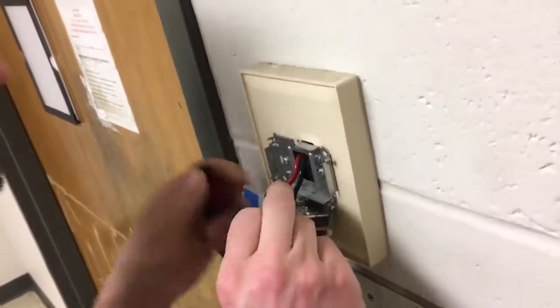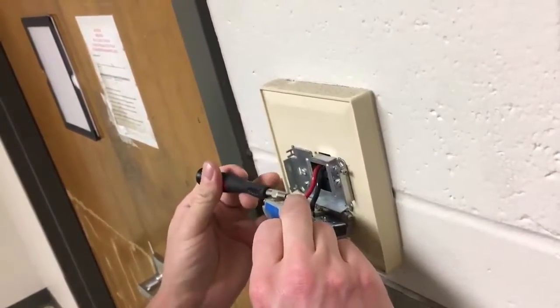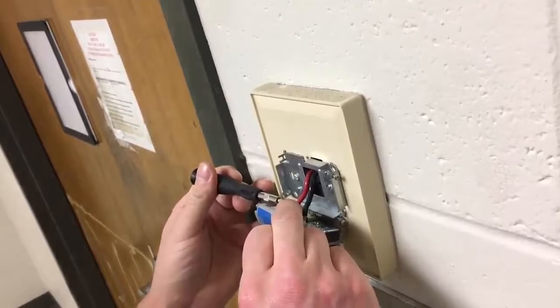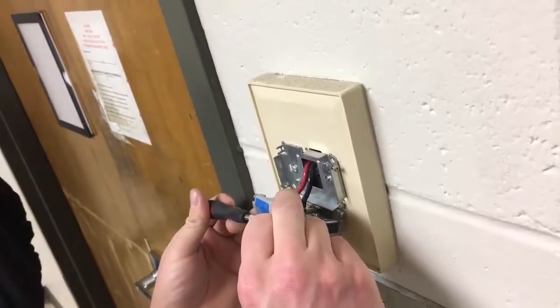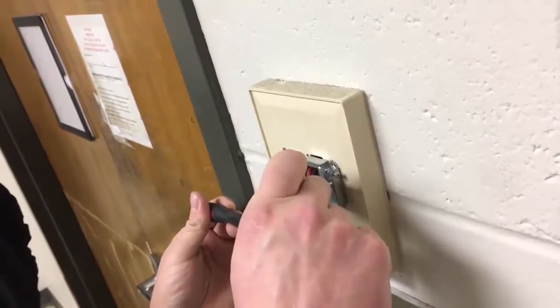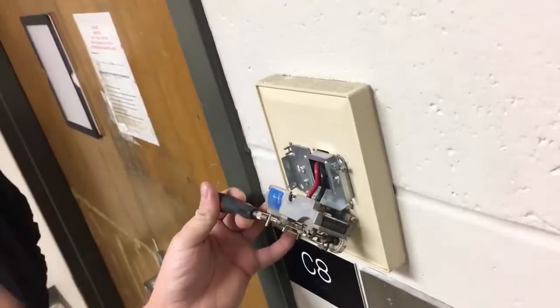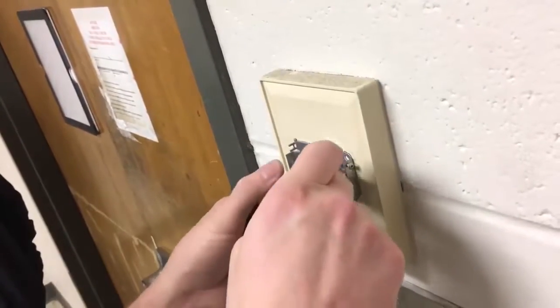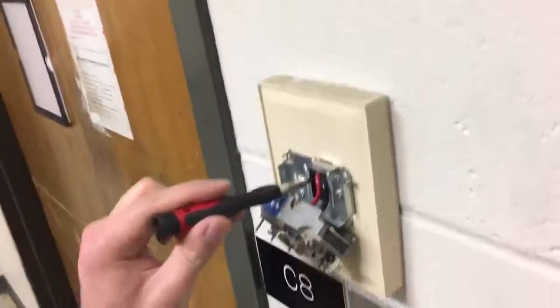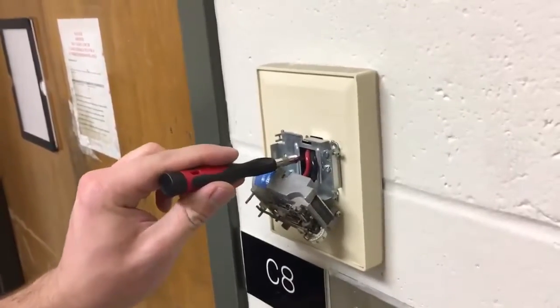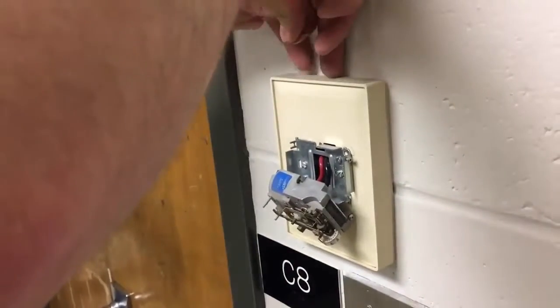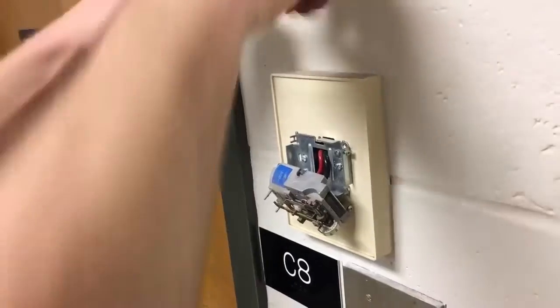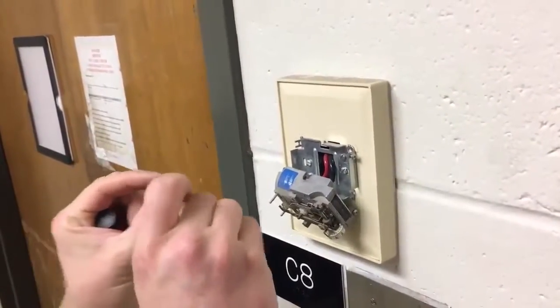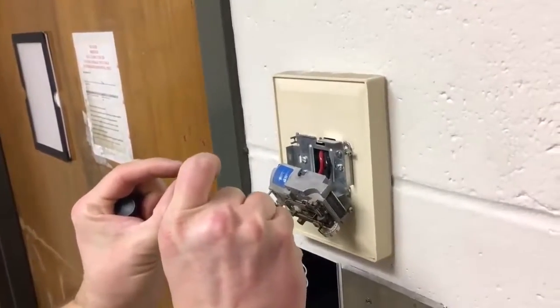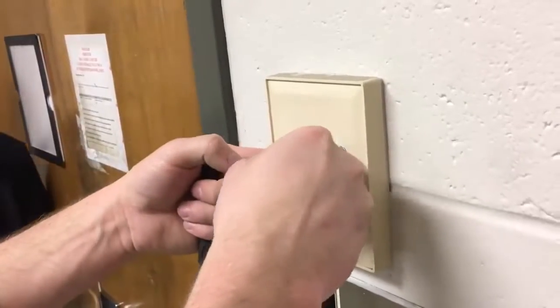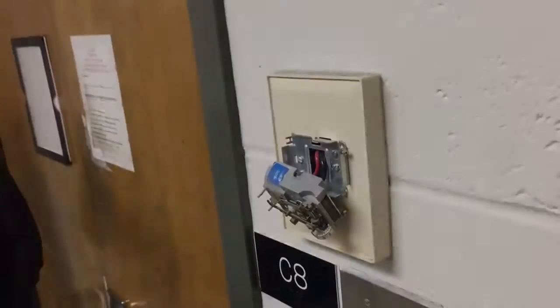They've got these color coded. The red is your supply air, 20 pounds, so that'll always have pressure on it. As this vents air, you'll stop sending air here, and you'll start discharging more heat. So that's your output line. Typically in the wall, there's a mounting bracket where you've got copper lines that come down and meet. They go to a mounting bracket that has two little ports on the front that these plug onto. Those ports can leak over time.